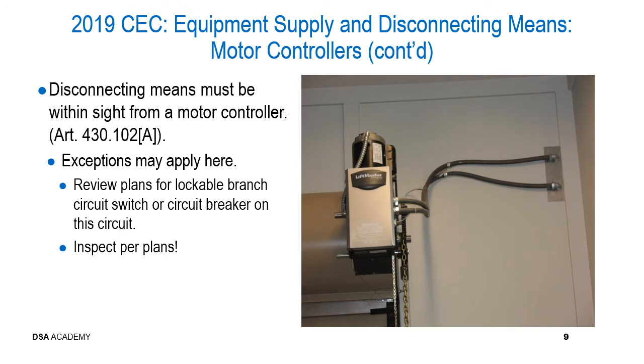The picture on the right-hand side of this slide shows a motor and motor controller unit for a roll-up door at a snack bar in a high school. Now, to look at this, you can see that this motor is basically hardwired from someplace inside the wall. And it's not apparent that there is a disconnect here. But again, the point is, even though Article 430.102(a) requires a disconnecting means within sight from a motor controller, remember that there may be exceptions that are available that may apply here. So it's important to review the plans for the lockable branch circuit switch or the circuit breaker on this circuit, because that may be identified there.